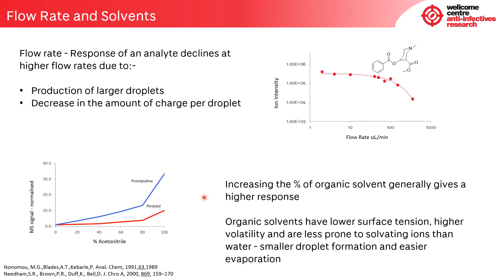Increasing the percentage of organic solvent in electrospray generally gives a higher response. Organic solvents have low surface tension, higher volatility, and are less prone to solvating ions than water. This leads to smaller droplet formation, easier evaporation, and an increase in the number of ions in the gas phase. The figure at the bottom shows the response of two compounds, protriptyline and pindolol, against an increase in the percentage of acetonitrile in the eluent, with the response of both compounds normalized to their response in 100% water. Both show a large increase in signal as the percentage of acetonitrile goes up, but as can be seen, the effect is very compound dependent.